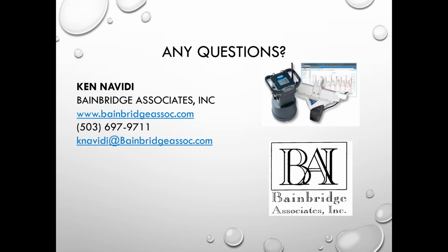A wet calibration would be putting this mag meter on a volumetric tank and running it through a flow facility. There are several places where you can have that done. Some of the meter manufacturers, like McCrometer, have a flow tank, so if you send the meter back to them, they'll calibrate it. I think Utah State has a flow facility, and they'll calibrate meters. And some cities actually have calibration facilities, like the city of Portland has their own, and they run it through their own calibrator. That's kind of the way that people do it.